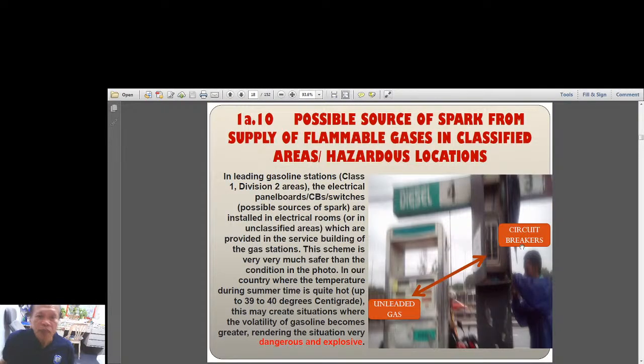Okay, I just want to show you that this is a wrong installation, where in a gasoline station, the owner and the contractor and the designer allowed the installation of a panel board with circuit breakers very close to a gas dispensing unit. This is a violation of the code. You do not install breakers that are very close to sources of flammable substances like this dispensing unit of a gasoline station. No way.